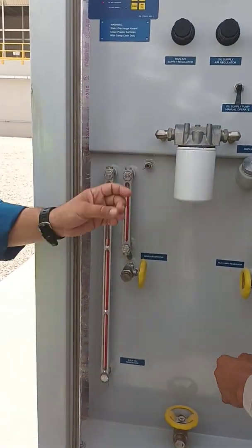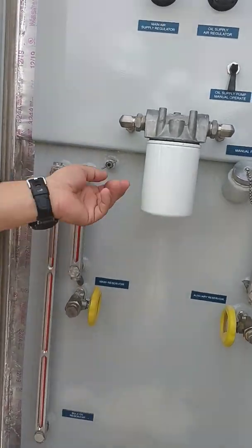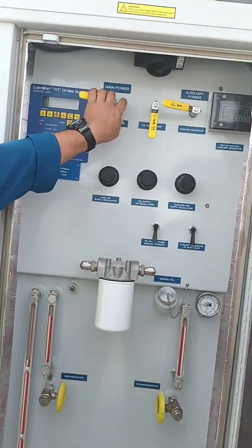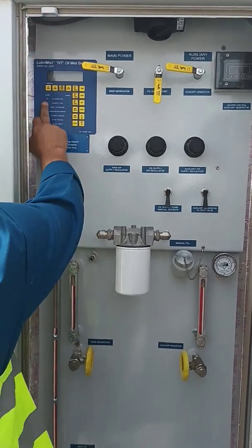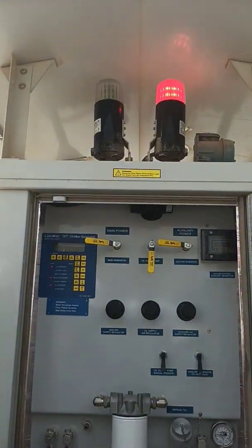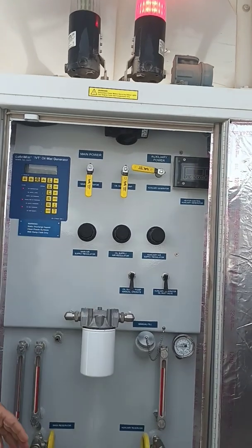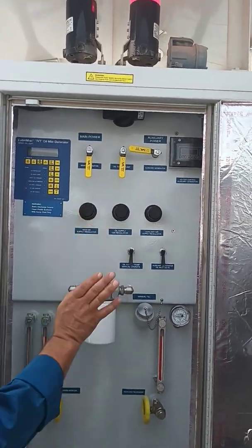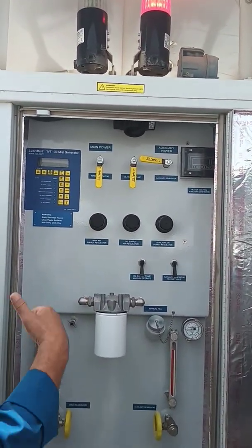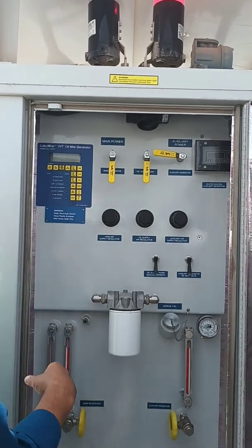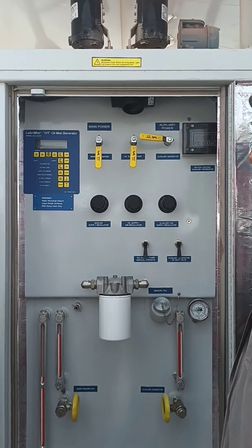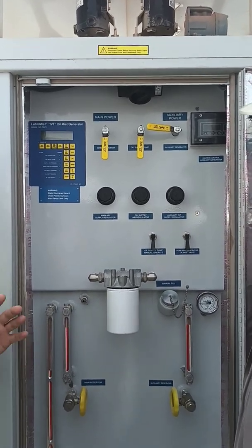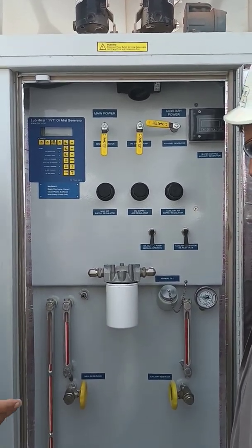This valve here, we call it an oil mist inspection valve. So now if I try to clear the alarms, I cannot clear them because everything has to be green. So if I open my air, everything will go back to normal because we didn't touch anything. Little by little the mist pressure is going up, 30 and so on, and it's going to reach 50 millibar. So 50 millibar is the most important part of the oil mist generator.